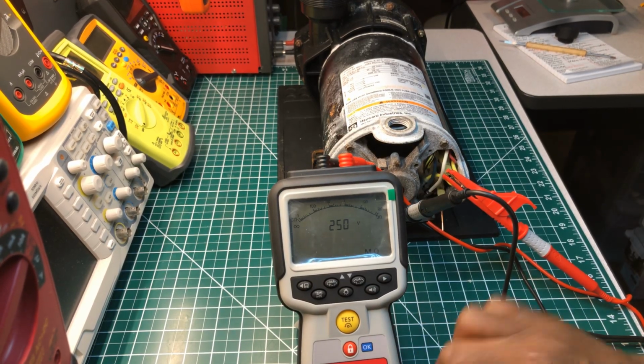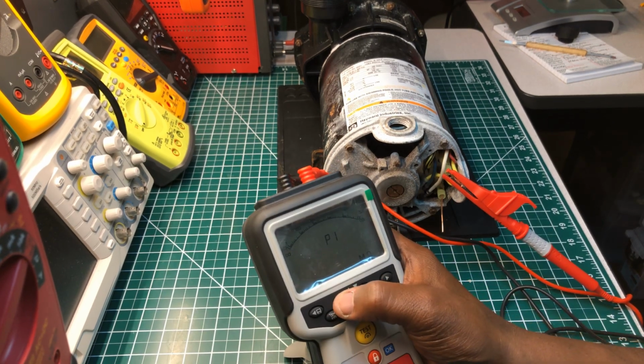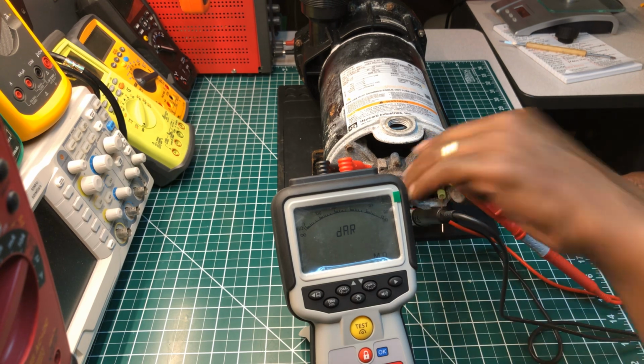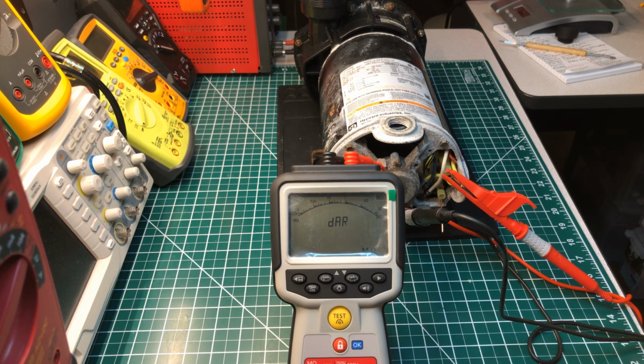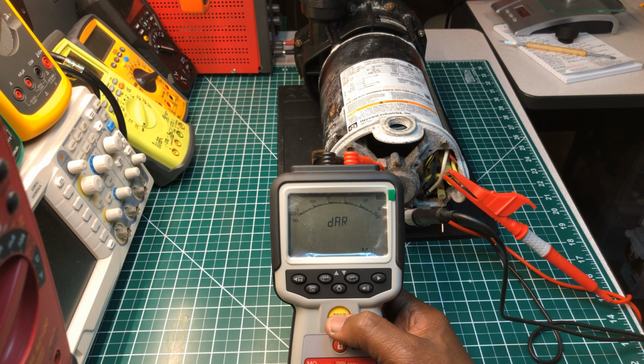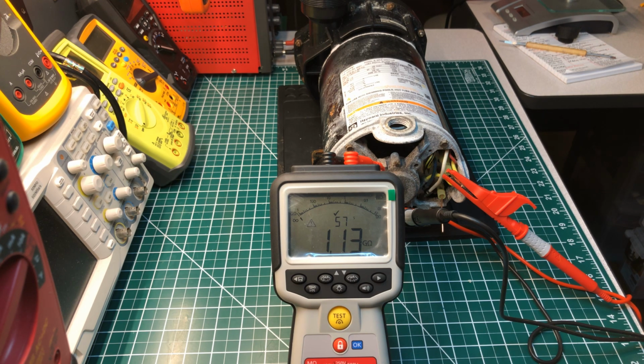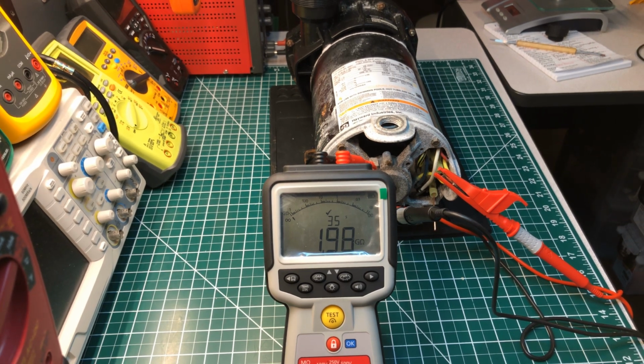All right. 250 volts. I'm going to do a DAR test. You guys can see that. All right, here we go. All right, it's counting down. Remember, the FLUKE had timed out because it was a greater value than what could be displayed on the meter. So it gave me that ERR on the display.